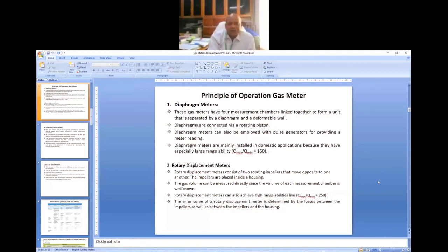A rotary displacement meter consists of 2 rotating impellers that move opposite to one another. The impellers are placed inside a housing. The gas volumes can be measured directly since the volume of each measurement chamber is well known. Rotary displacement meters can also achieve high rangeabilities like diaphragm meters, and the ratio of maximum to minimum might go up to 250. The error curve of a rotary displacement meter is determined by the losses between the impellers as well as between the impellers and housing.